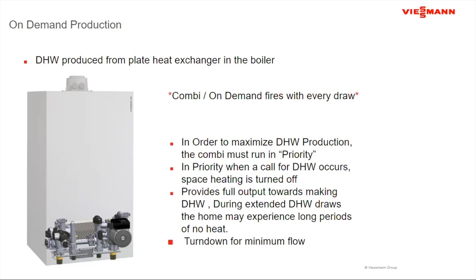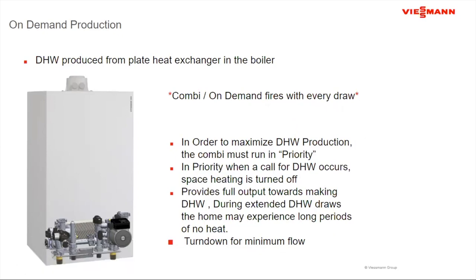And that means that if I start to look at long periods of generating hot water with a combi boiler, since there is no storage to cycle with, you may run for a long period of time without space heating going into the building. So that is always a concern when I do a combi boiler. The other thing is that it fires with every draw or every demand. The combi boiler not only has to meet the maximum demands of the building, but it also has to meet the minimum demands. A number to think about.